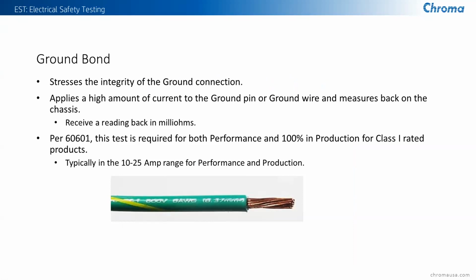Starting with ground bond. Ground bond is probably one of the simplest tests to perform. It basically tests the integrity of the ground connection from the input safety ground to any of the metal housing and metal components that make up the device. To do that, we pass a regulated current through the ground conductor while monitoring the voltage across it, and then we can calculate the resistance of the conductor. By doing that, we can determine that it is an adequately rated wire or conductor to meet the requirements. This is again a fairly simple test to do. We have a variety of equipment that can handle that, and I'd be happy to go into more detail if you need it.